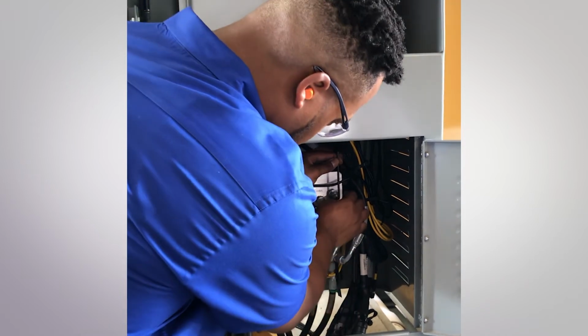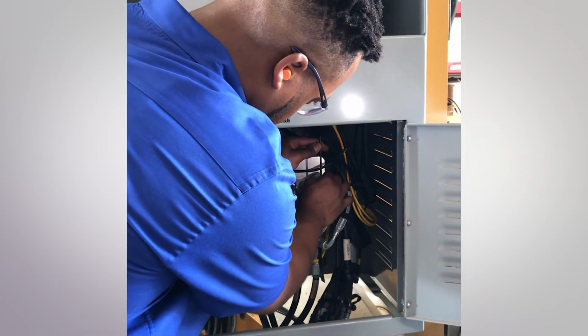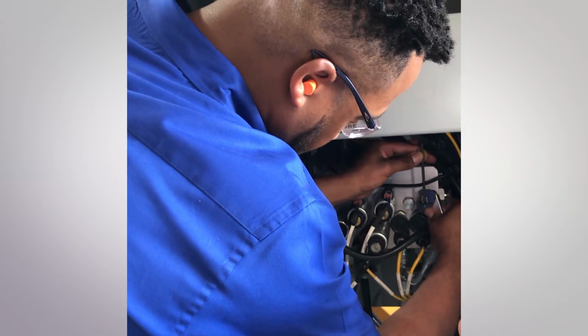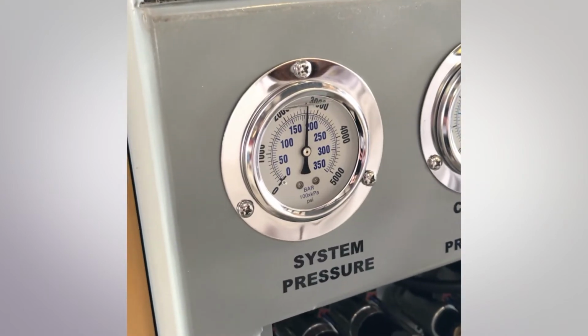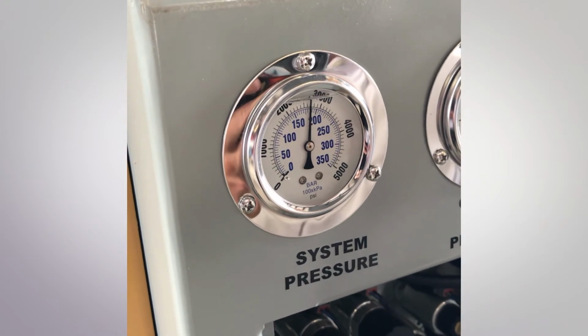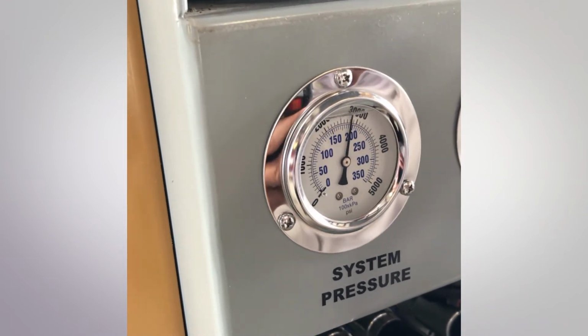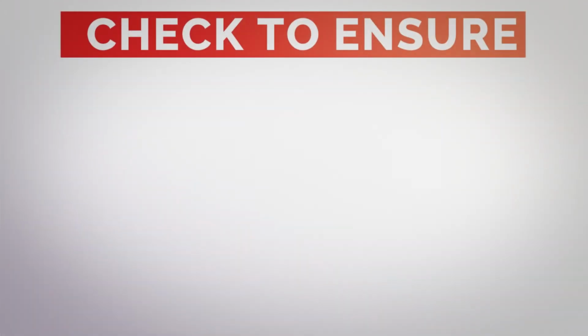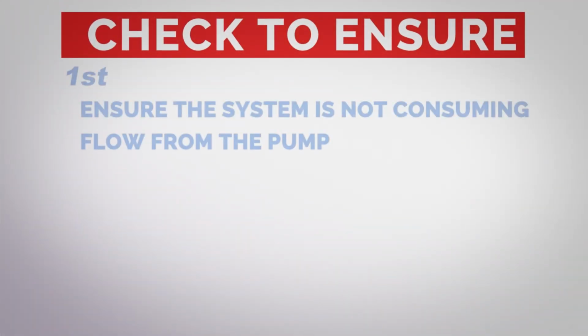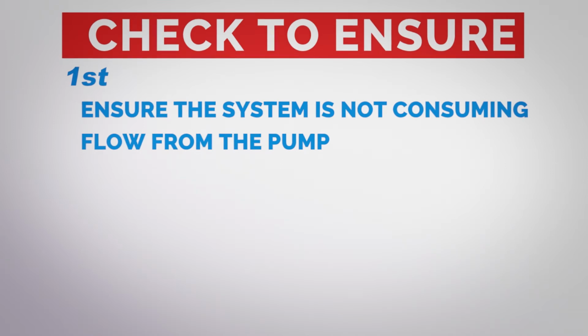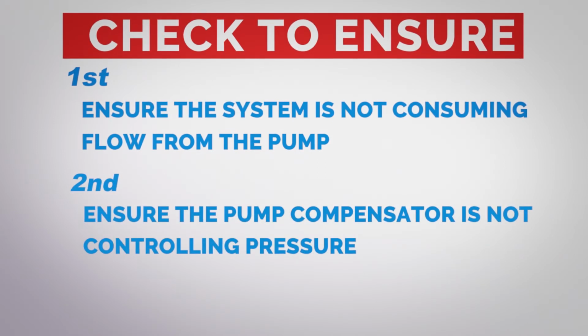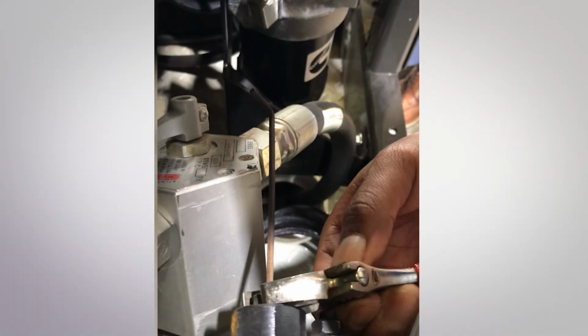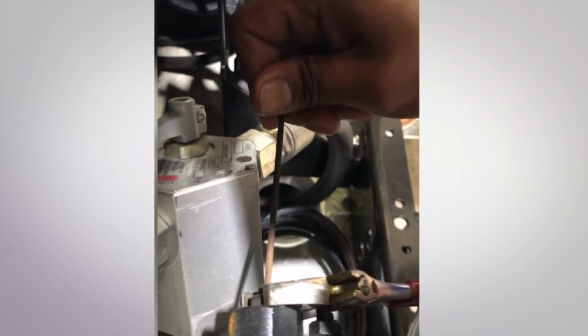The first setting to adjust is the relief valve pressure. Increase your relief valve setting until you are 250 to 300 psi above your desired system pressure. It is important to note that all components in your system must be rated to handle the higher pressure. If you are unable to get the system pressure 250 psi above your desired system pressure, check to ensure the following two things. 1. Ensure the system is not consuming flow from the pump. 2. Ensure the pump compensator is not controlling pressure. If it is, increase the pressure setting slowly until the relief valve can be properly set.